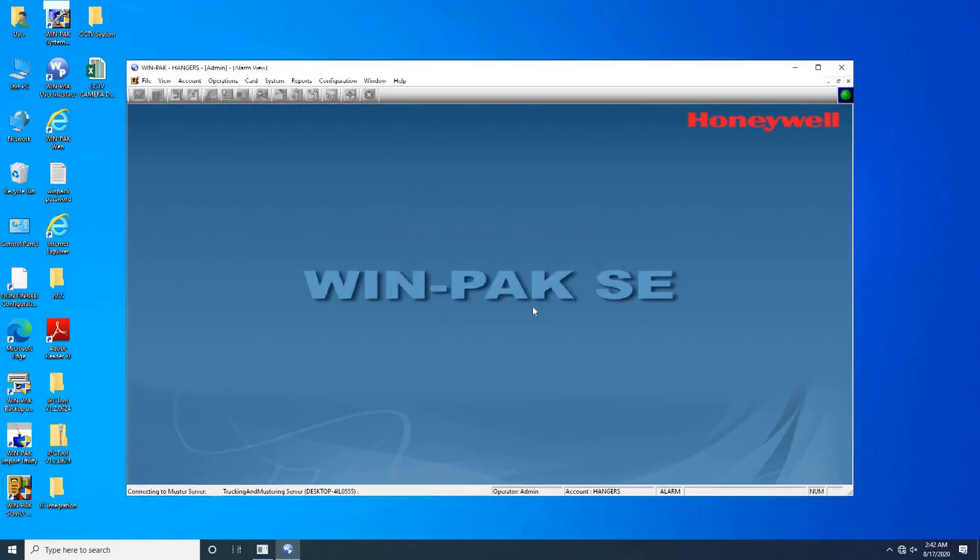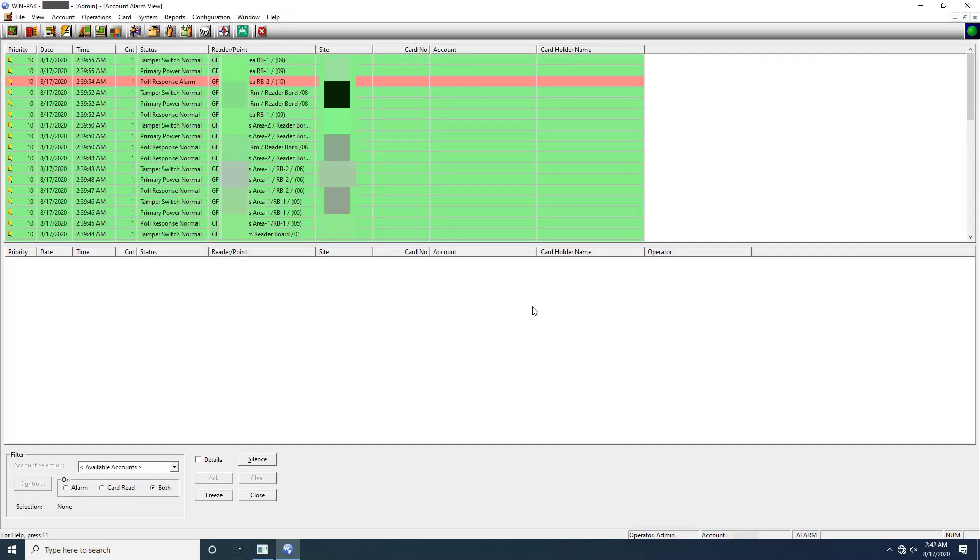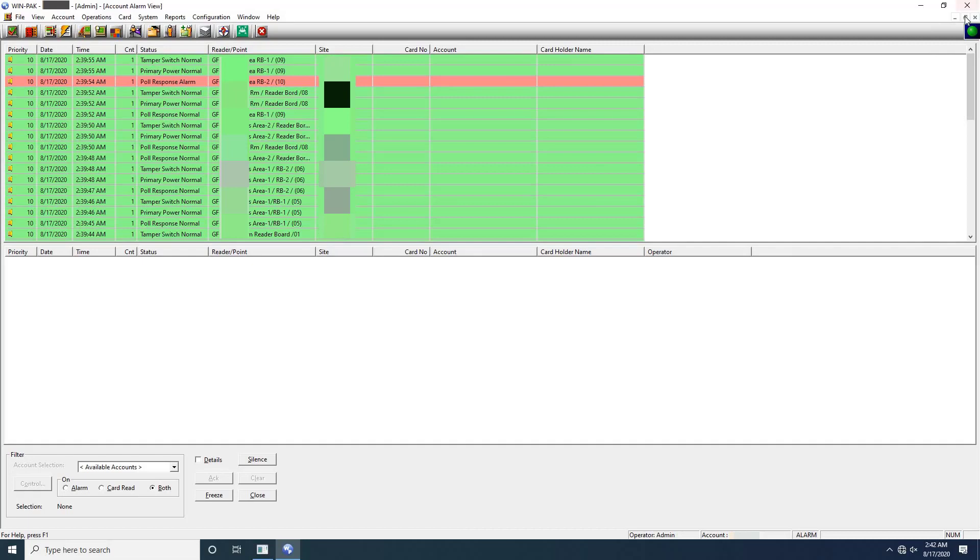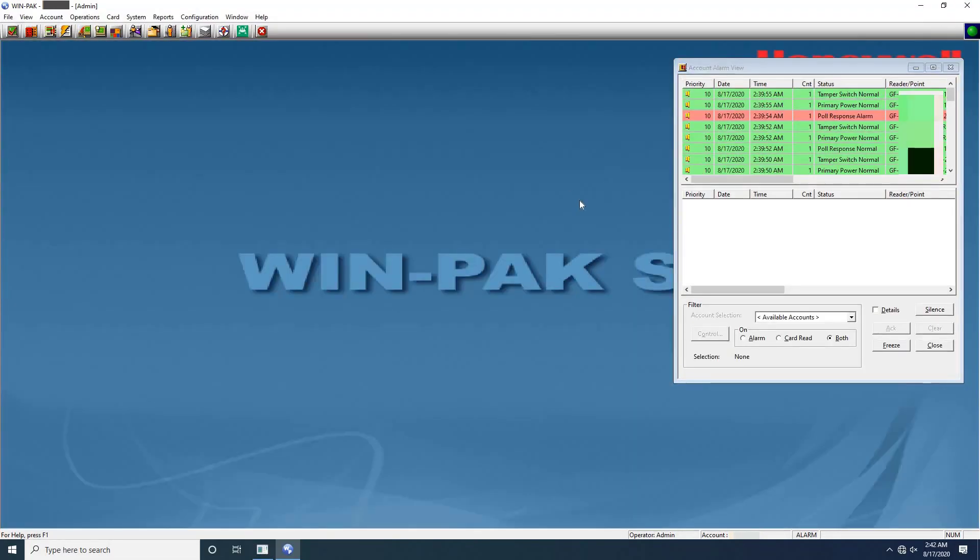Once logged into the software, by default the alarm view window displays. Alarm is an event or an access control activity that must be acted upon as soon as it occurs. The alarm view window displays alarms when they occur and continues to beep the sound until it is acknowledged. The alarm view window is divided into two horizontal panels. Incoming alarms are displayed in the upper panel according to priority and time. The color of an alarm indicates the state of an alarm. Keep this window aside for some time, and let's add IC board into WinPak.